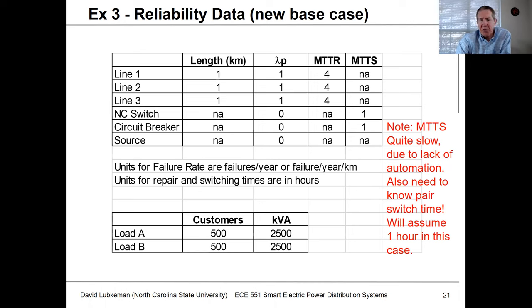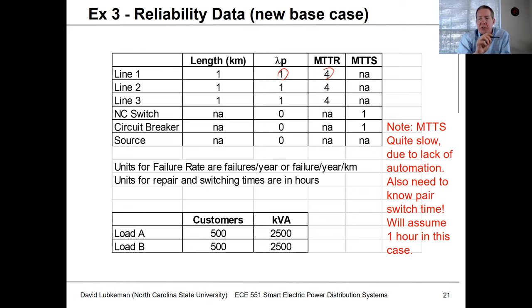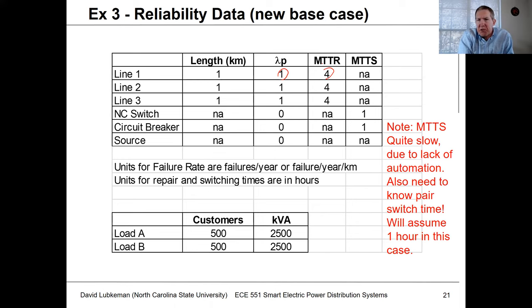For this new data set, I'm looking at permanent faults only — one fault per year per kilometer, taking four hours to repair — and I'll use those same statistics for each of the different line sections. There are no temporary faults shown in this case because for temporary faults, those are typically cleared and don't result in many SAIDI events. With switching operations, we're usually focused more on permanent faults, because when we have manual switches those will all involve sustained outages anyway.